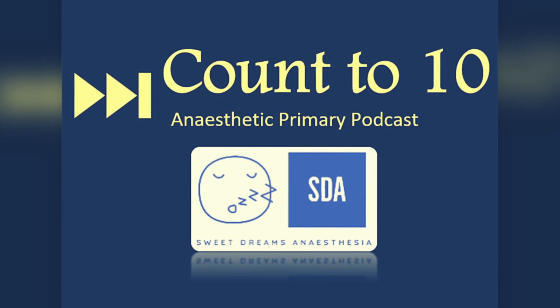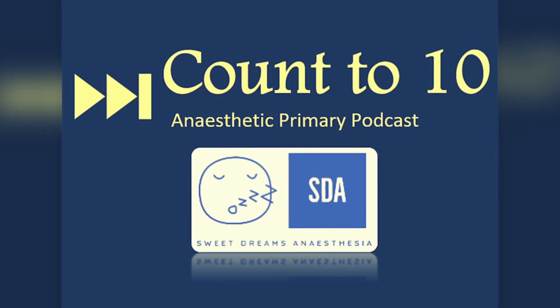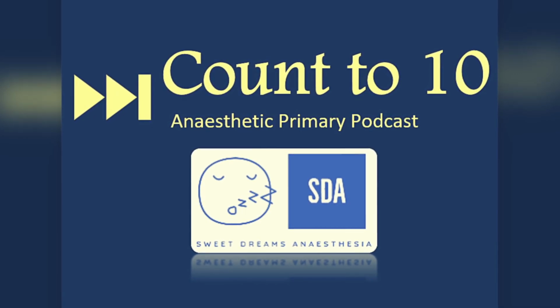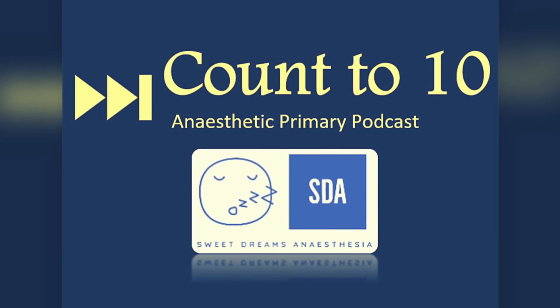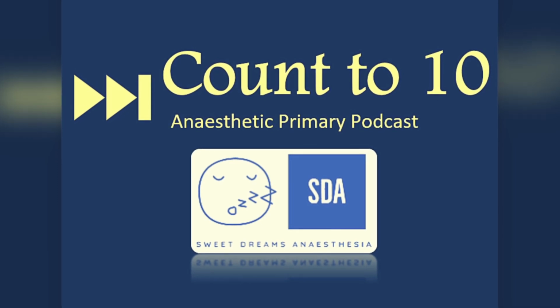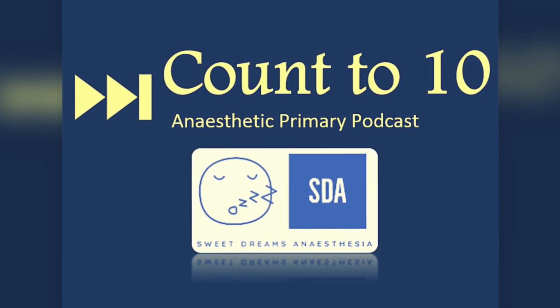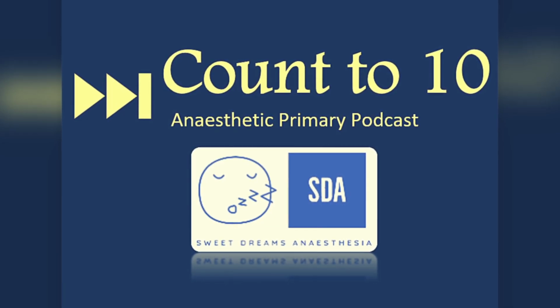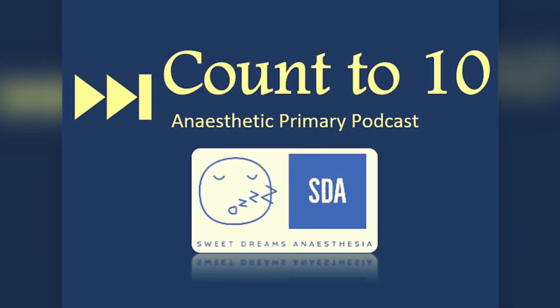It's quite convoluted, but essentially it's working on the principle that we're measuring what the patient is exhaling, we know what the patient is inhaling, and we're making an assumption of what the patient's normal nitrogen concentration was before they started inhaling an oxygen mixture. So the only thing left that we don't know was what was the volume of the patient's lung before they started inhaling the oxygen mixture. So that's the only variable that we don't know, and if we know all the other variables, we can rearrange for that variable. And what that gives us is what the volume of the lung was before the patient started inhaling plus the FRC, and we can then do some equations and take that away to give us just the FRC.